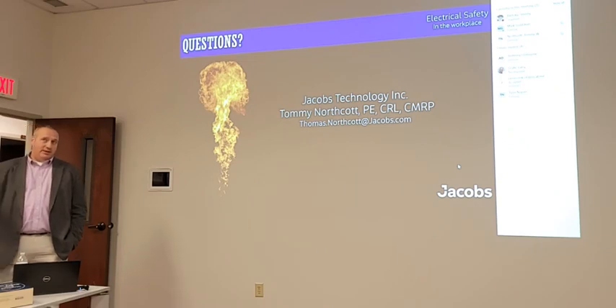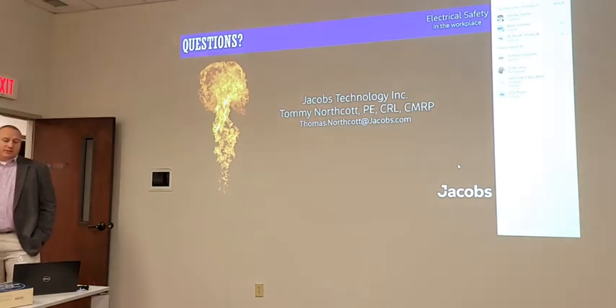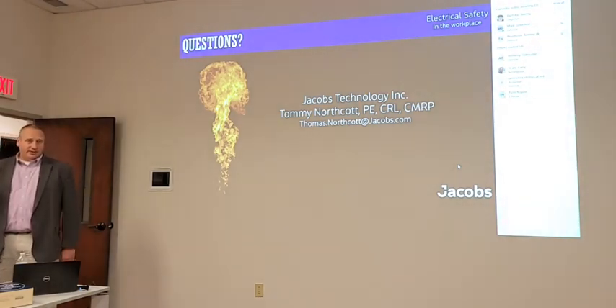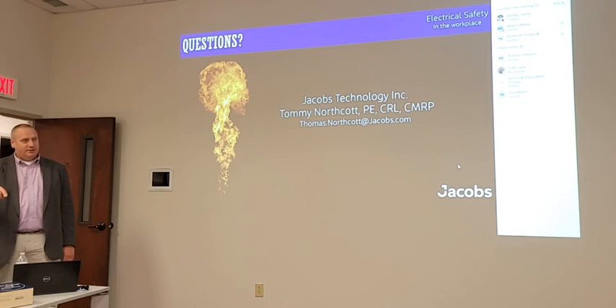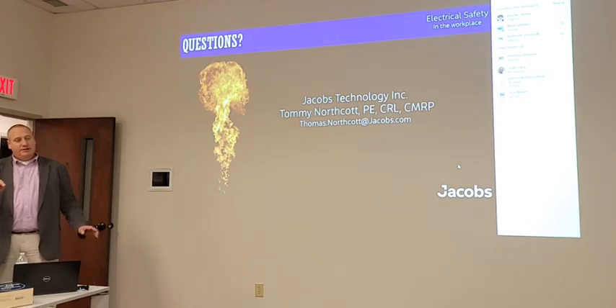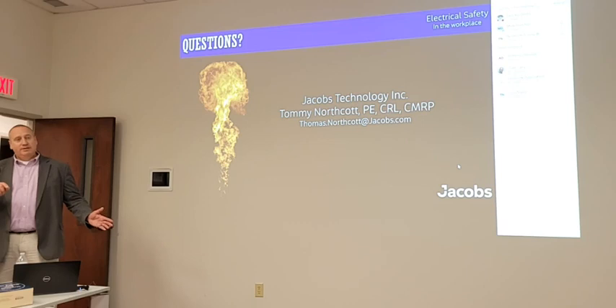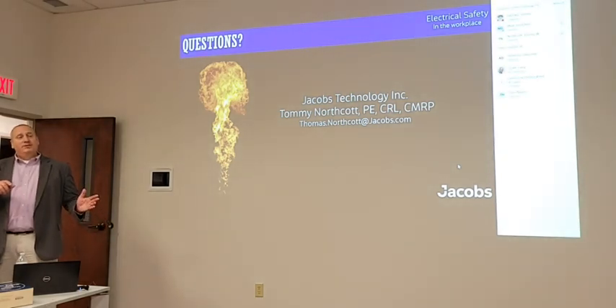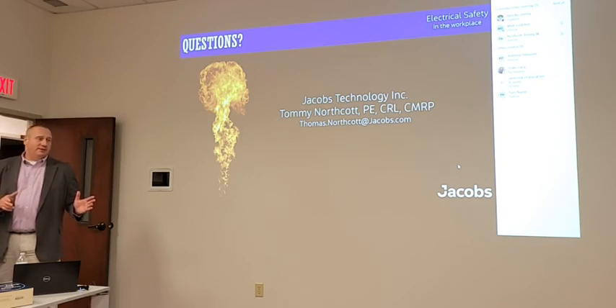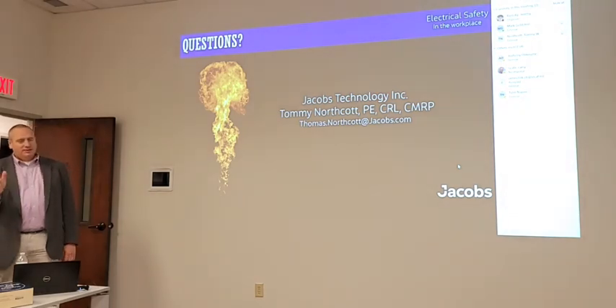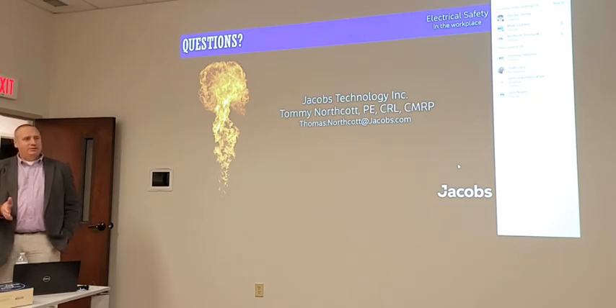The intentional operation is where there's an operator somewhere making a conscious decision: I'm going to open this breaker, I'm going to close it. In that case, the expectation is to somehow verify that somebody's not in front of that breaker. Now, if you've got a scenario where a pump is monitoring pressure and it drops below a certain amount and it automatically turns on, I can't think off the top of my head of anywhere that's specifically addressed. To me, that goes back to the tripping aspect: the probability of you walking by there and it coming on and having an arc flash would be so improbable that you wouldn't have to worry about it.